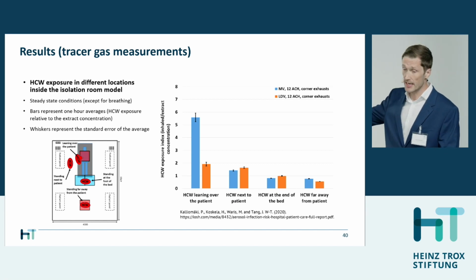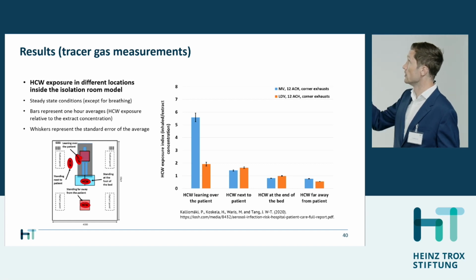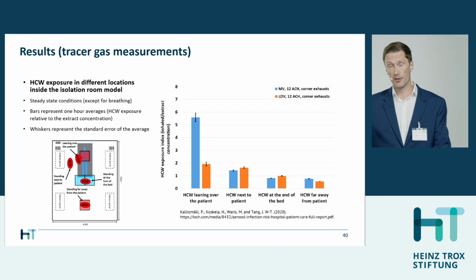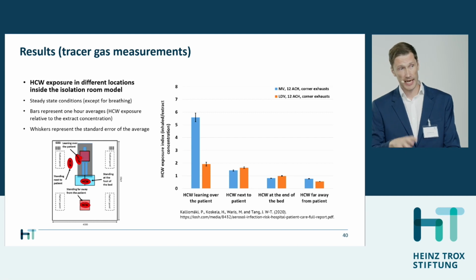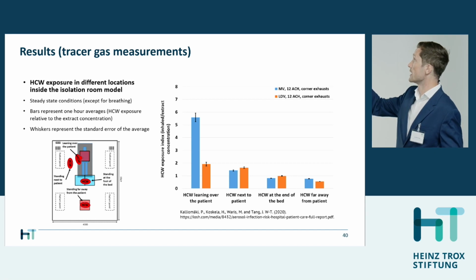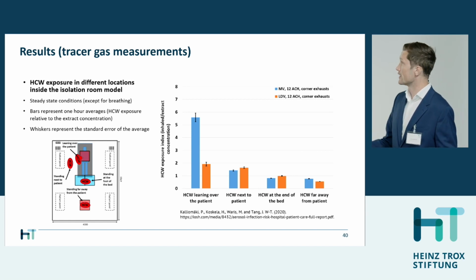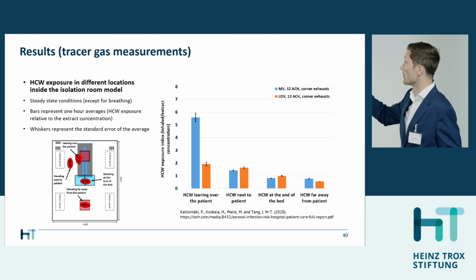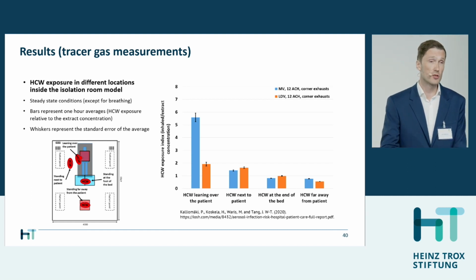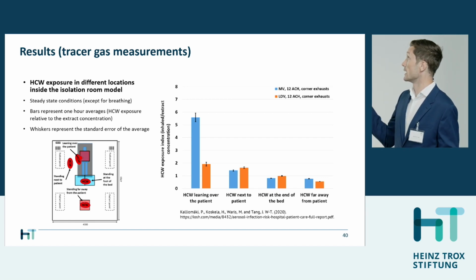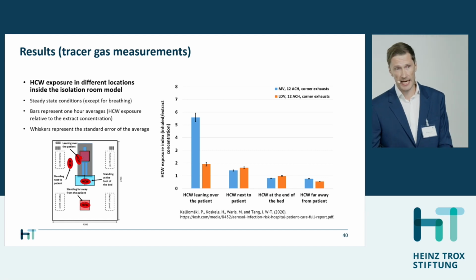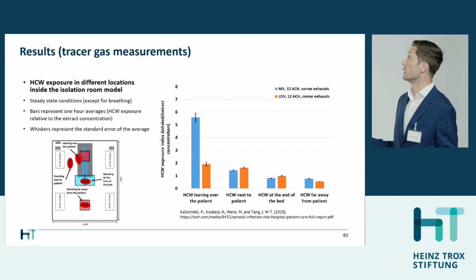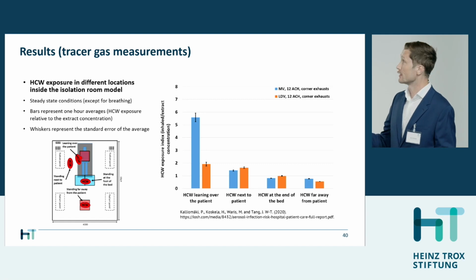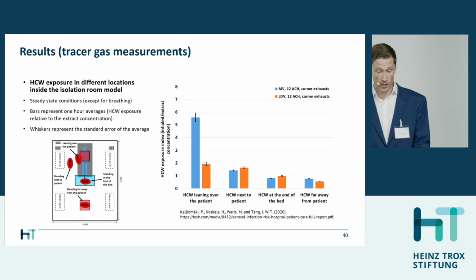And on the right, you can see the exposure results. I'm not going to go into the detail about the scale of the exposure, but what should be noted is that the higher the bar, the higher the exposure of the healthcare worker to the patient exhaled air. In this figure, the blue bars represent the typical mixing ventilation case, and the orange bars depict the local downward ventilation case. What you can see directly is the obvious result that the further away you go from the patient or the source, the lower the exposure. But you can also clearly see that when the healthcare worker was close to the patient, giving care, leaning over the patient, the exposure was significantly higher with the typical mixing ventilation case. Or vice versa, it was significantly lower with the local downward ventilation case.